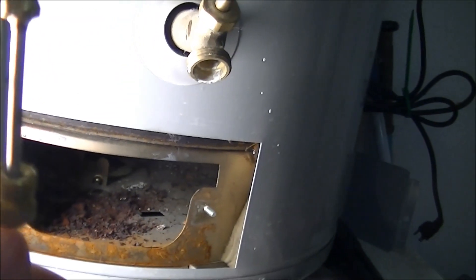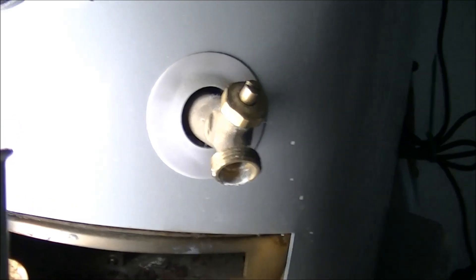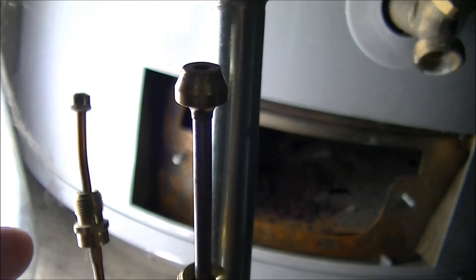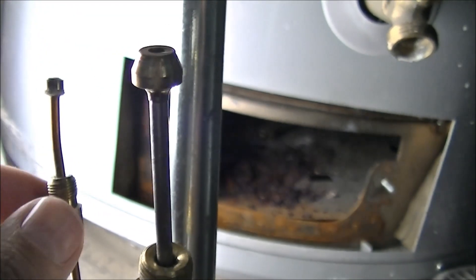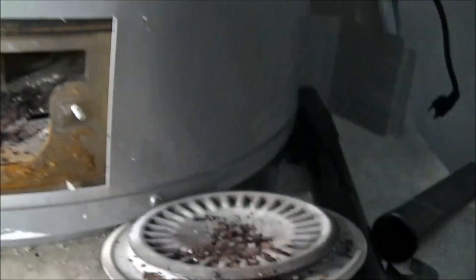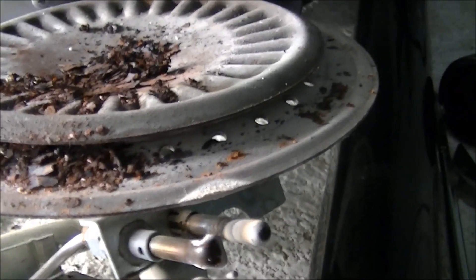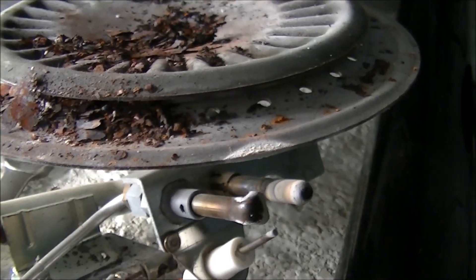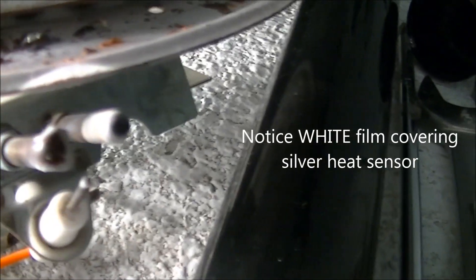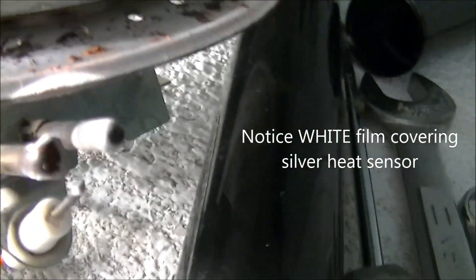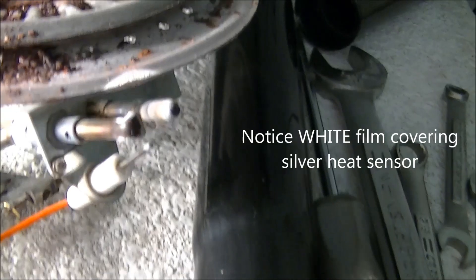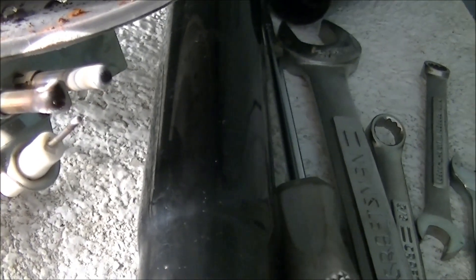controller: the pilot light gas, the regular gas, and the heat sensor. Here's the burner. I'm going to have to vacuum off the rust so it'll get a nice good flame. But the problem I'm having, I believe, is with the heat sensor. It's got some corrosion on it. You can see it's got a white discoloration.